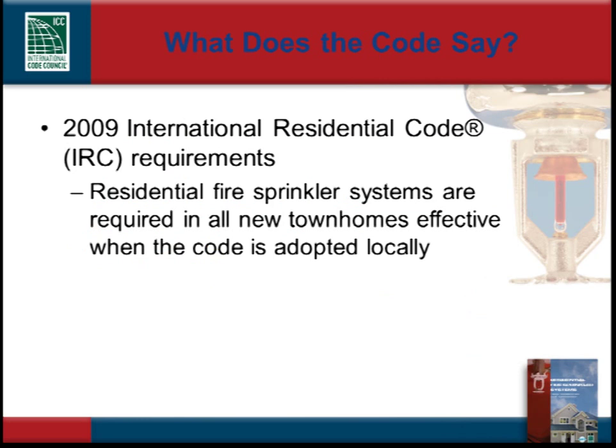Specifically, the IRC states that an automatic fire sprinkler system is a life safety component required in all new townhomes. For townhomes, the requirement for residential fire sprinklers takes effect upon adoption of the 2009 IRC. The requirement applies to townhomes regulated by the IRC, which are those limited to three stories in height.